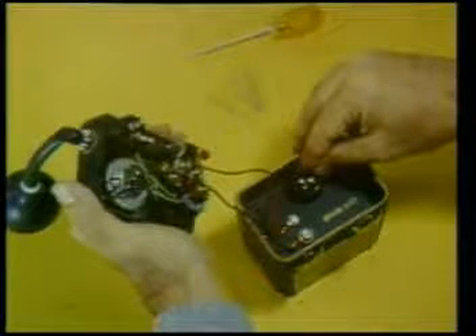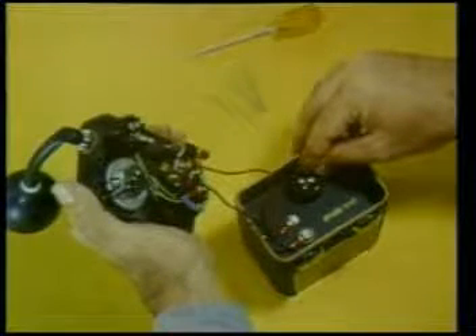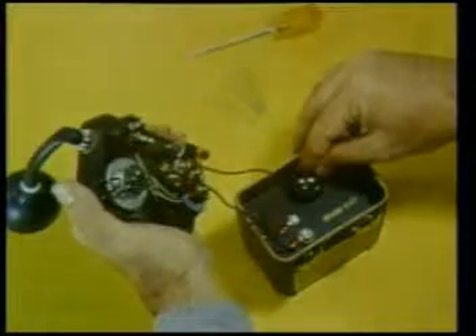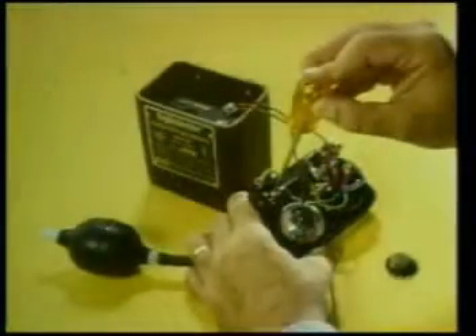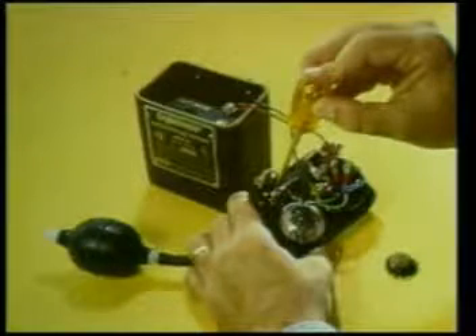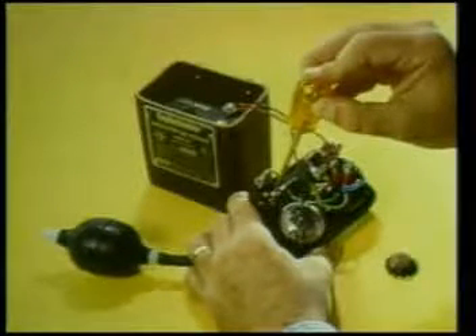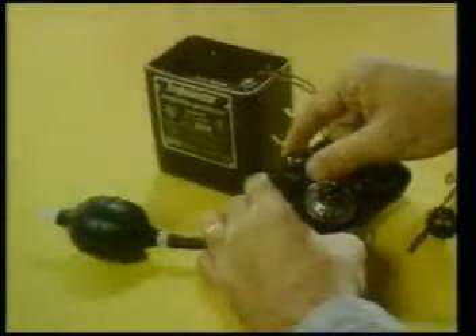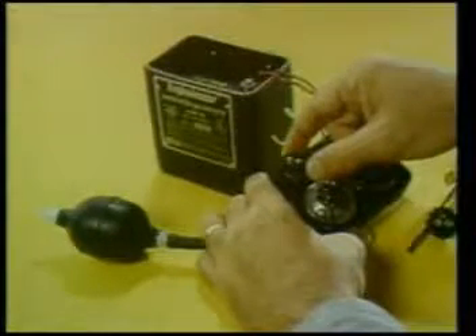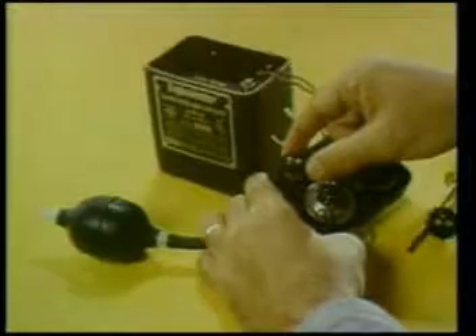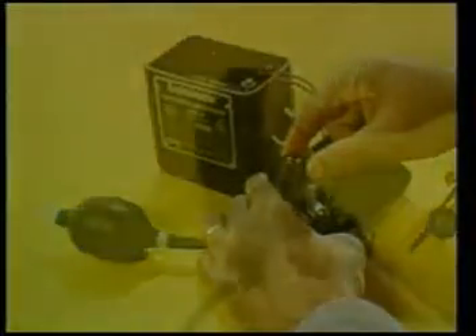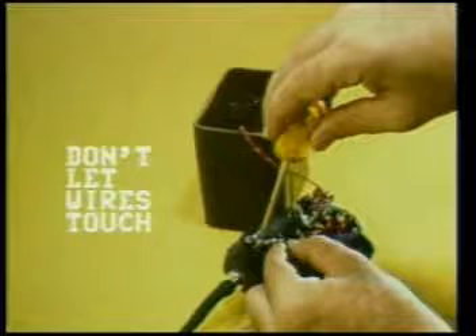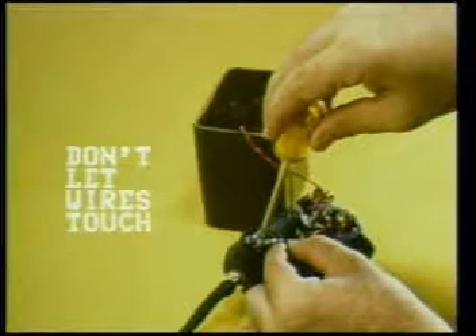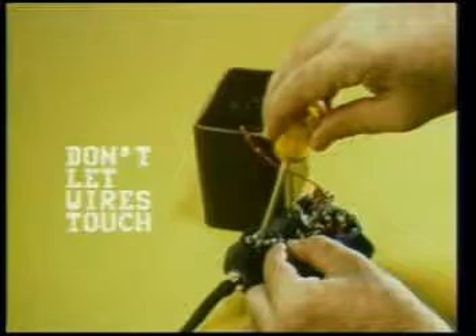To replace the filament, remove the 3 screws that hold the top cover in place. You'll find a spare detector filament is stored in the case. Remove the 2 green wires from the terminals on the top of the detector filament and unscrew the detector filament. Make sure that the new filament is screwed firmly into the chamber and that the gasket is clean and properly seated. Reconnect the 2 green lead wires firmly. Be sure that the terminal lugs and wires do not touch each other. And remember to replace the spare filament inside the case as soon as possible.